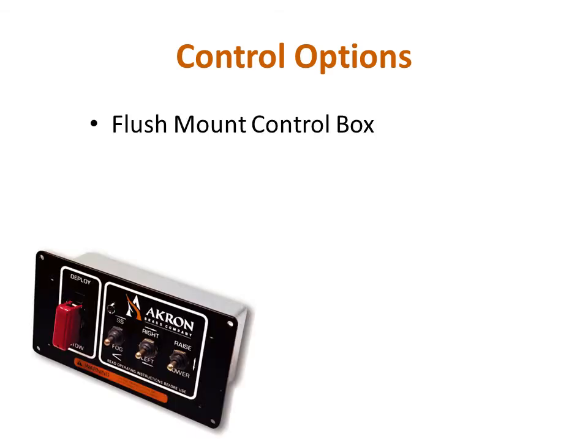There are several controls available for the StreamMaster which can be used either individually or combined to give multiple control options for a single monitor. The standard controller for the StreamMaster is the flush mount control box with stow and deploy. This is typically mounted on the pump panel and has switches to stow and deploy the monitor, as well as rotate and elevate the nozzle and control the flow pattern if used with an electric nozzle.